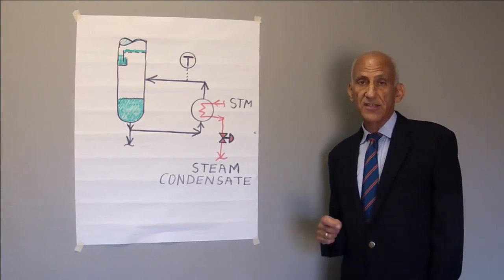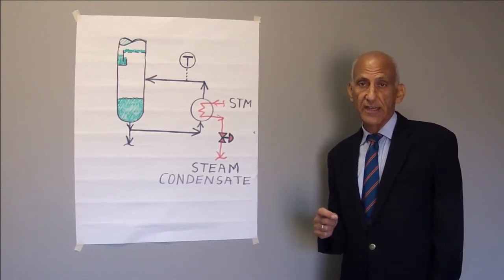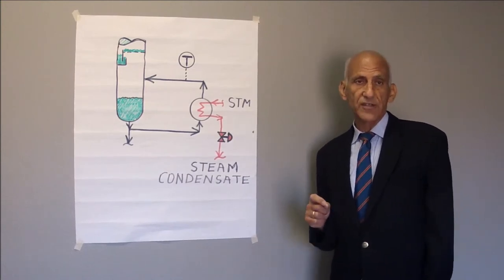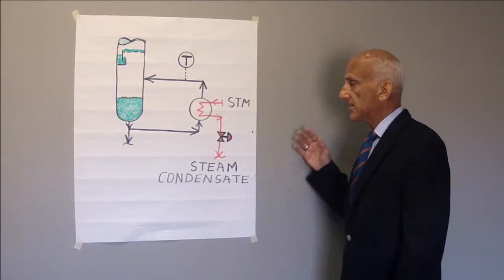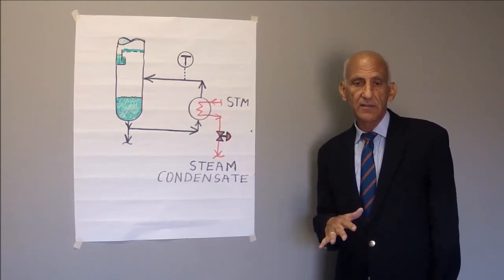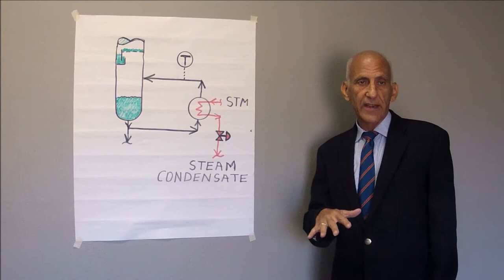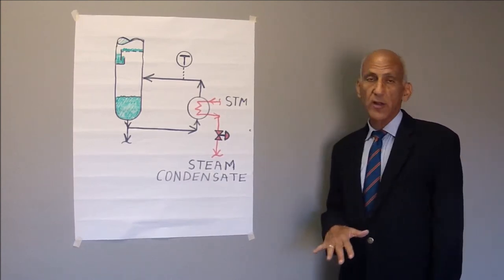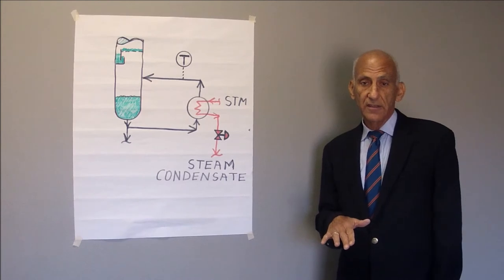And whereas high-velocity aids sensible heat transfer, apparently high-velocity retards latent heat transfer. And as the steam blows through tubes and blows the condensate seal out, the heat transfer rate is going to go down and the reboiler duty will go down.